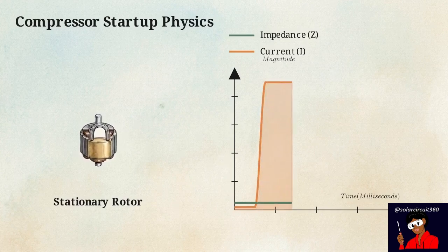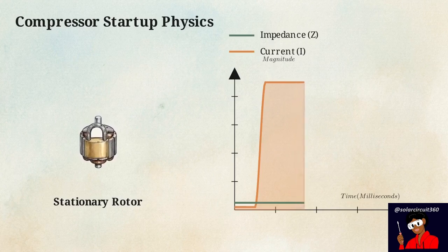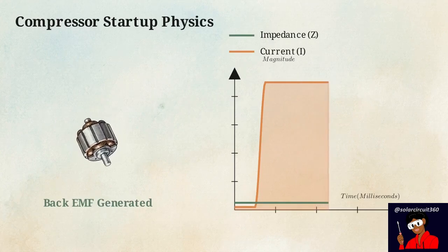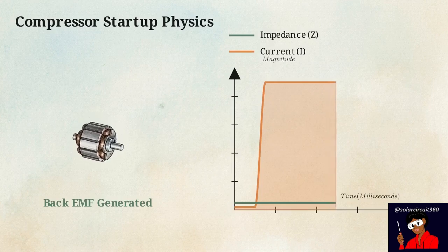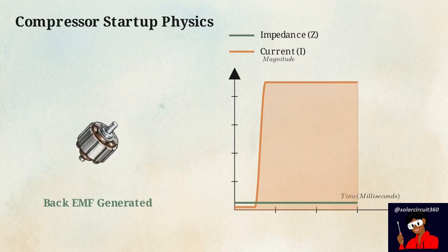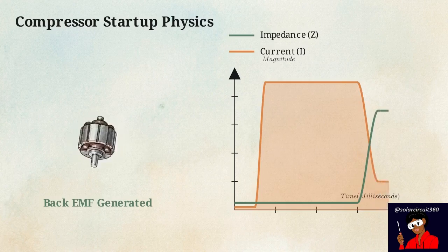The instant the compressor tries to start, a massive, unrestricted wall of electrical current floods the motor to overcome the rotor's weight. It is identical to forcing open a heavy mechanical lock. You apply maximum physical force to achieve initial movement. The exact millisecond the rotor turns, it generates back EMF. The impedance sharply rises, forcing that massive current spike down to a stable operating level.